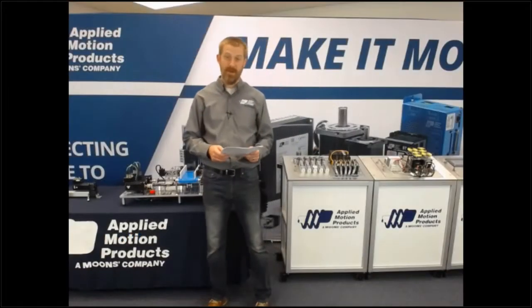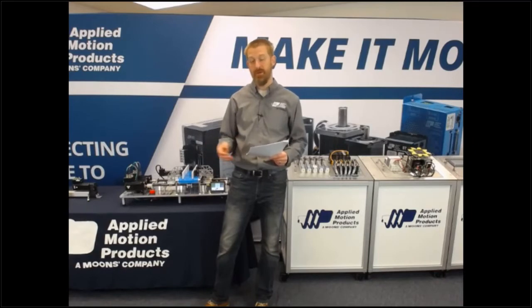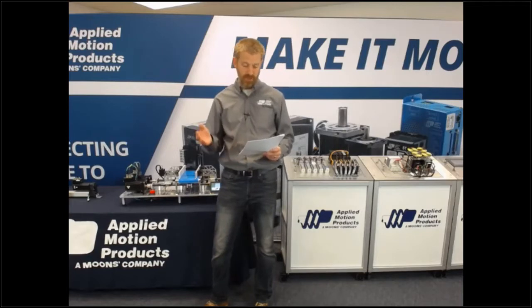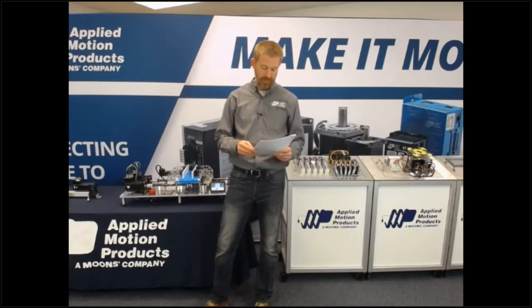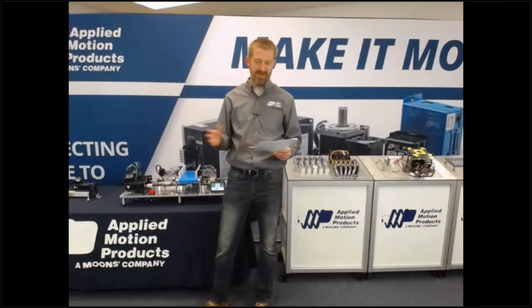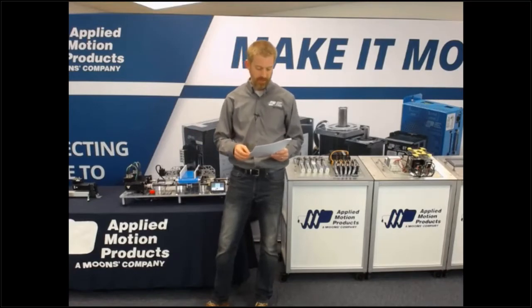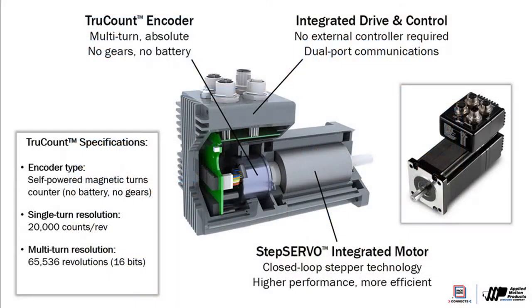I want to talk today about our TruCount Absolute Encoder. Absolute encoders as a category are encoders that can resolve their position even after the motor and the drive they're connected to are powered off. This is compared to an incremental encoder, which can only track motion as a delta step from its previous position. In other words, an incremental encoder can tell the drive it's moved 100 steps since last time you asked, but has no idea what that means — it relies on the drive to keep track of the real position. An absolute encoder, on the other hand, knows that it's currently 100 steps away from its predefined home location and can communicate that back to the drive.